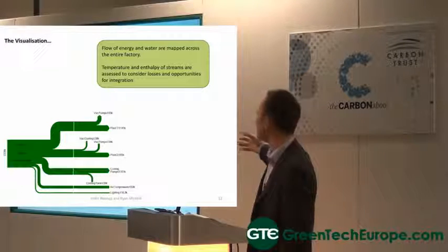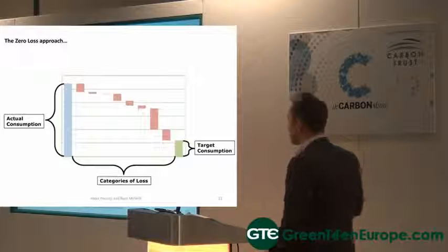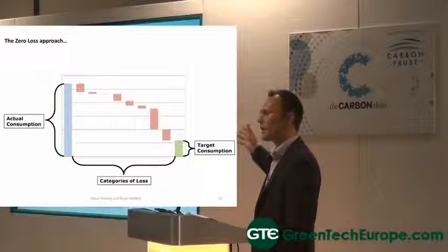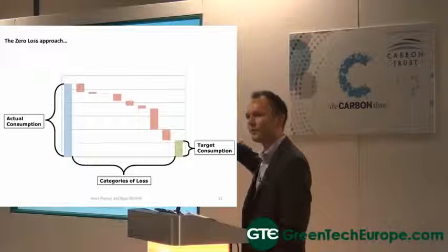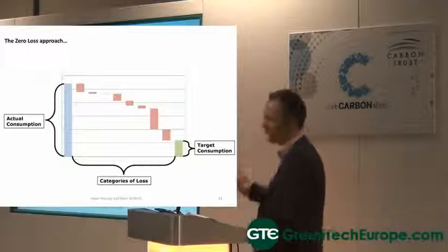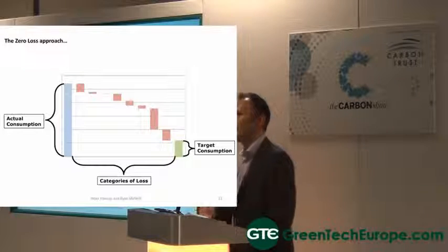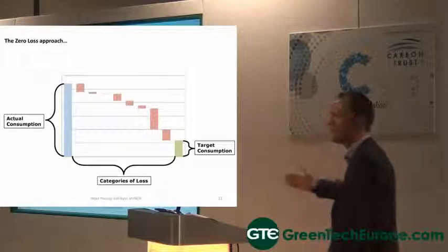We can also calculate the energy of these streams further in the process — steam coupling and energy recovery. What's important for Nestlé is the reduce, reuse, and recycle model. When we're looking at energy saving projects, it's quick to jump to new technology or heat recovery. But what we need to challenge holistically is how the assets are being operated. This is an example of an evaporator — some losses here are from design, and these losses here are from operations. When we look at businesses seeking return on investment, we automatically step towards capex. But in reality, with good metering and understanding of how our assets operate, there are still easy gains to be made around how we operate — temperature, pressure, idle mode, shutdown, changeover.